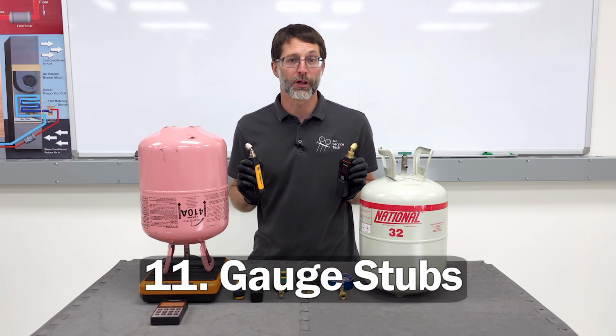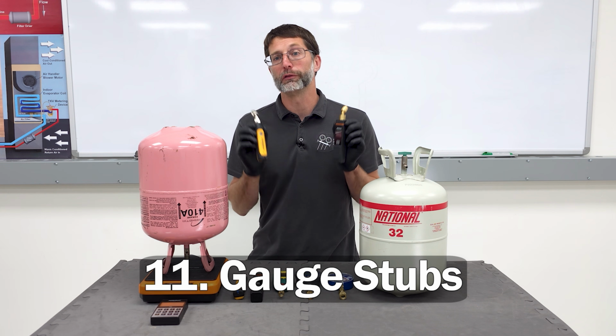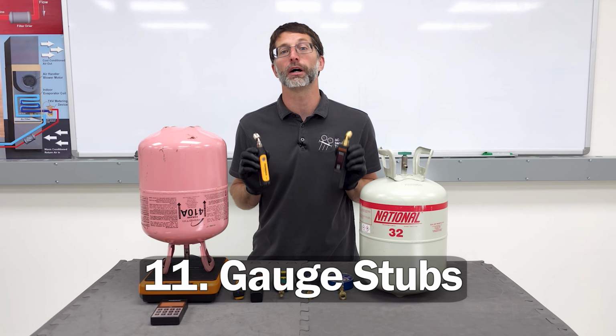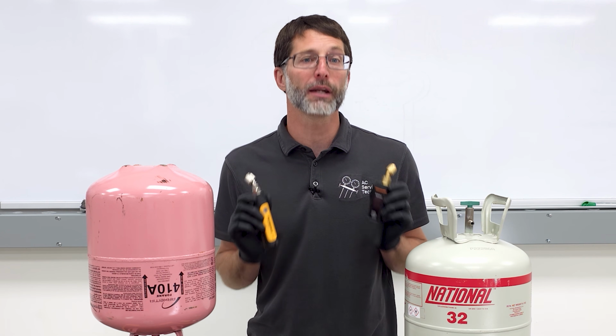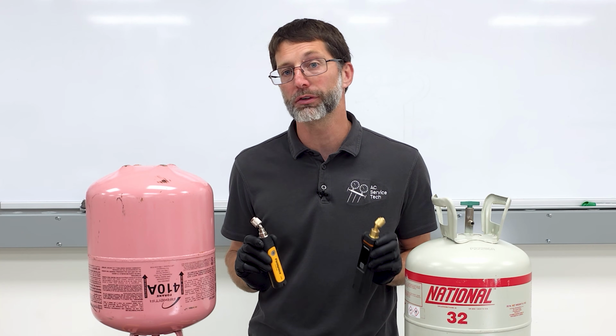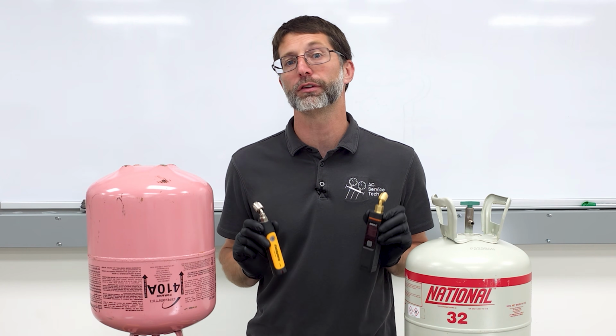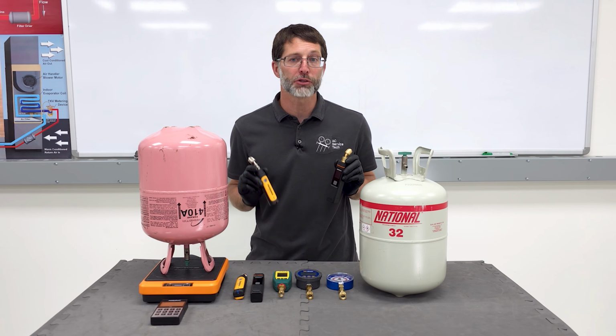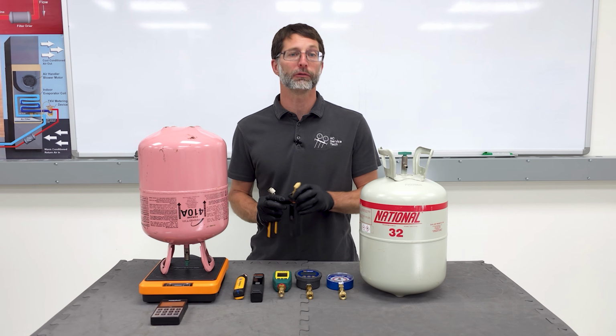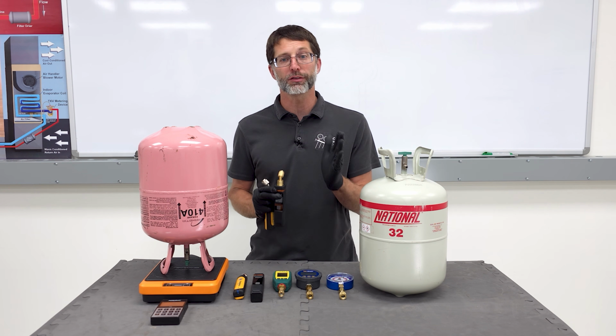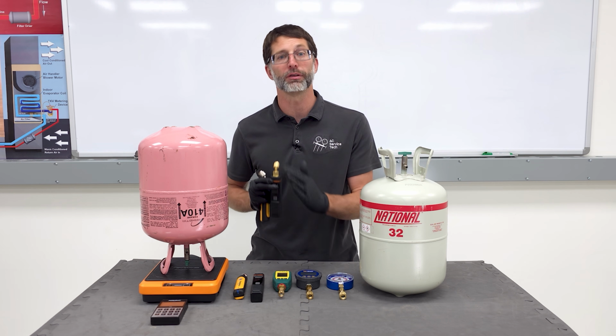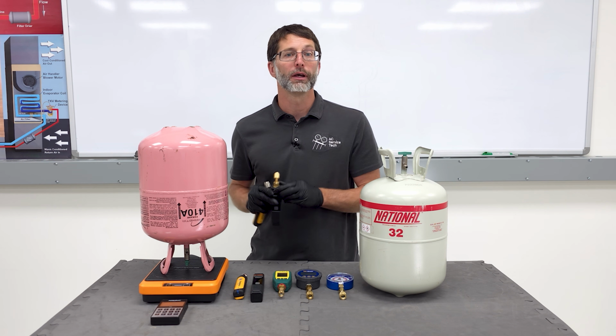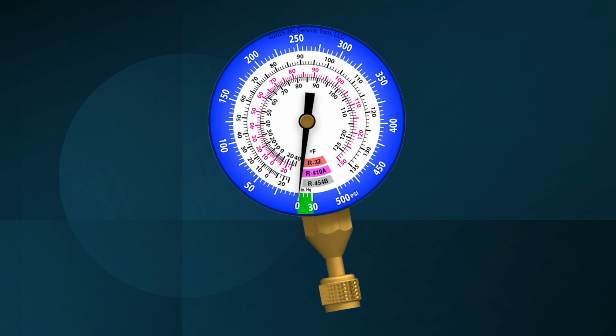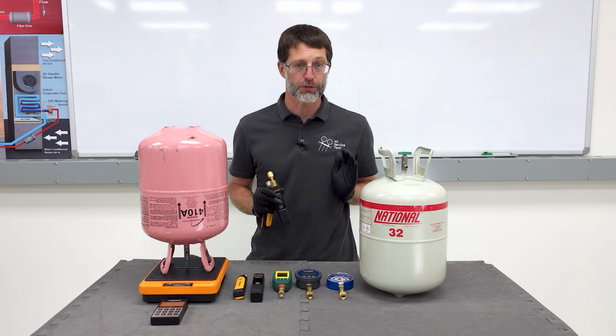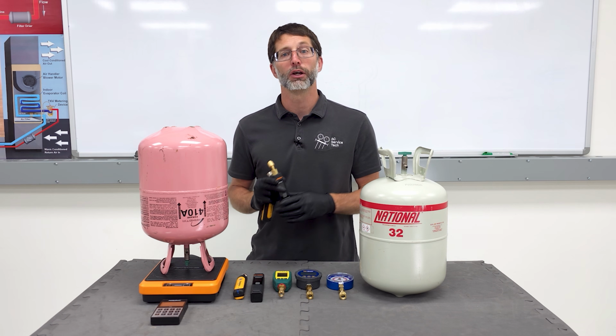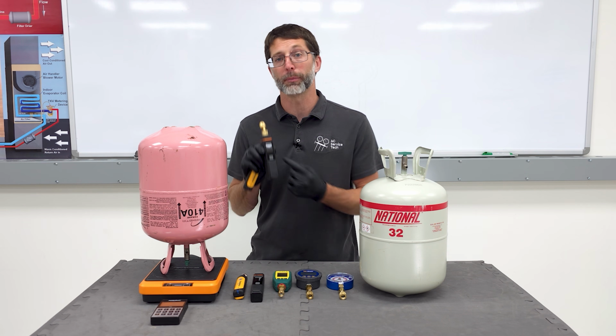Section 11, gauge stubs. Tool manufacturers have improved refrigerant pressure temperature measuring devices over time. Likewise, new procedures and methodology have been employed to reduce procedural time, increase accuracy, and reduce system contamination. Because of this, tool manufacturers and technicians are switching from manifolds with hoses to gauge stubs, also referred to as test gauges, and wireless probes. Gauge stubs can be found with either a compound gauge face or digital gauge face. For the sake of accuracy, use digital gauges whenever possible.